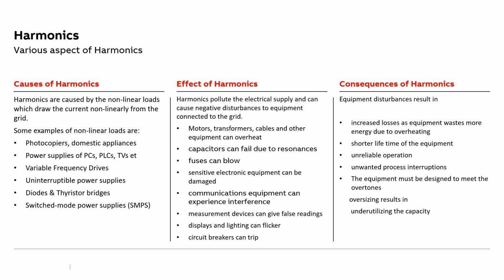So normally, whenever the system is being designed, these harmonics are taken into consideration, so the system is over designed. The transformer is designed so that it can take care of this additional harmonic load. Plus the cable sizes are selected accordingly, and your switchgear is selected accordingly. So overall, this oversizing has to be done, which ultimately results in underutilization of the overall capacity, and it's a wastage.